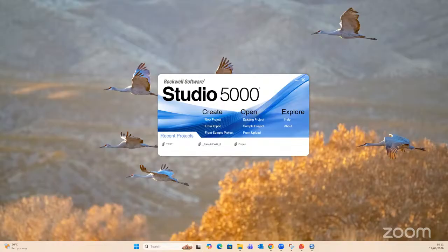However, because of how strict Rockwell is with programming, the fact that we have programmed this with Studio 5000 version 33, we would not be able to open that program with RS Logix 5000, because RS Logix 5000 stopped on version 21, right? So you won't be able to open it. And even any lesser version before 33, you won't be able to open that file.